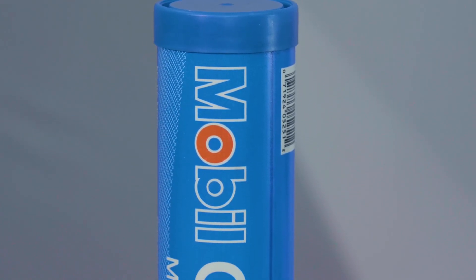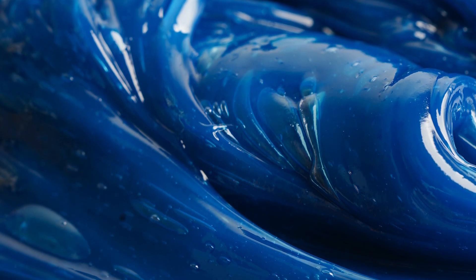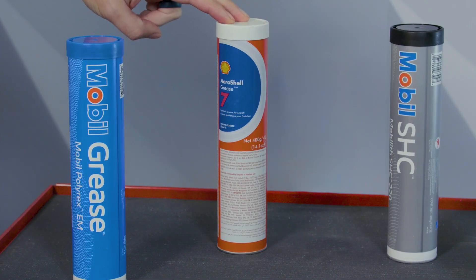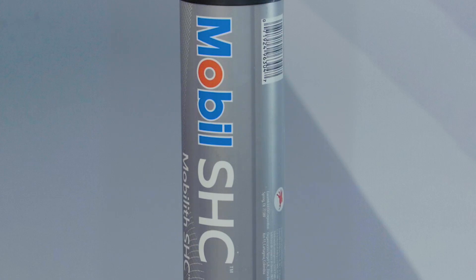Different greases serve different applications. Baldor Reliance Motors standardized on the Mobil Polyrex EM. This is a polyurea-thickened grease combined with high-quality mineral oil, yielding excellent performance and life across most electric motor operating speeds and temperatures. In exceptionally high ambient conditions, a high-temperature grease is used, such as Dow Corning 44. DC 44's lithium soap with silicone oil can handle the extreme temperatures of ovens, kilns, and such. When Baldor Reliance Motors are used in extreme cold conditions, such as arctic climates or flash freezers, Aeroshell 7 is recommended. This micro-gel thickened grease with synthetic oil is rated for use to negative 73 Celsius. Another example is heavily loaded applications, where Mobilith SHC 220 is used to satisfy the higher viscosity needs of roller bearings.